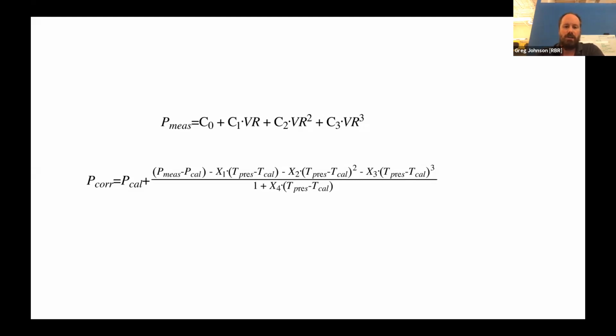And they mean that we can get 0.05% full scale accuracy across the entire temperature range from -5 to 35. That again is a datasheet number. It's a bit like our time constants, and we like to put conservative numbers on datasheets. When we ship the instruments to you, they're typically accurate to about 0.01% of full scale. But that allows the instrument to have a little bit of drift in that first year over which we say the calibration certificate is valid for.